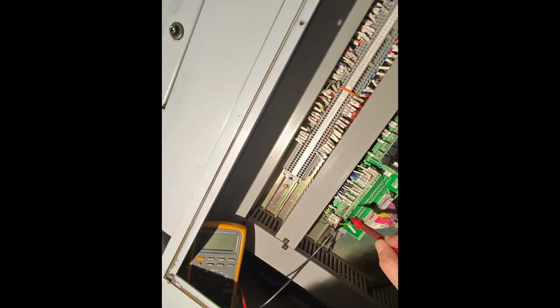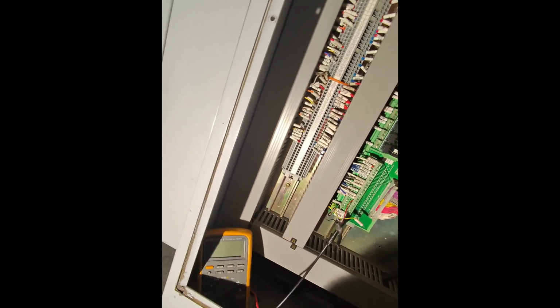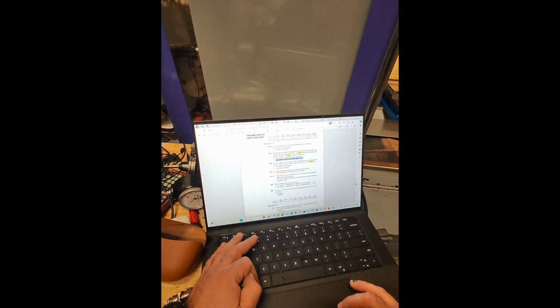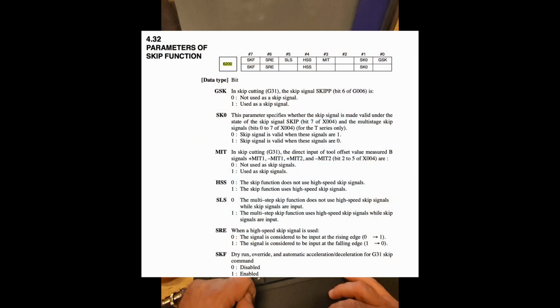So this way I also have to invert the signal to read the trigger on the falling edge rather than the default rising edge. I'll show that in the control in a second. Parameter 6200 bit 1 is how you specify whether you want to trigger on a 1 or a 0.